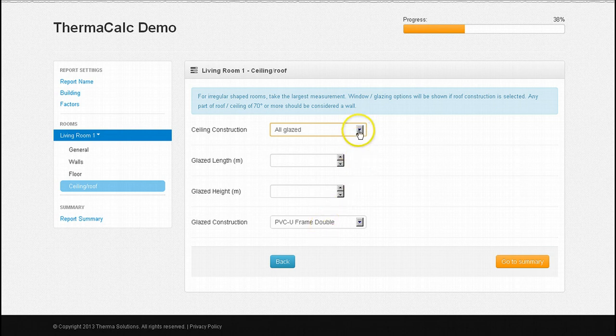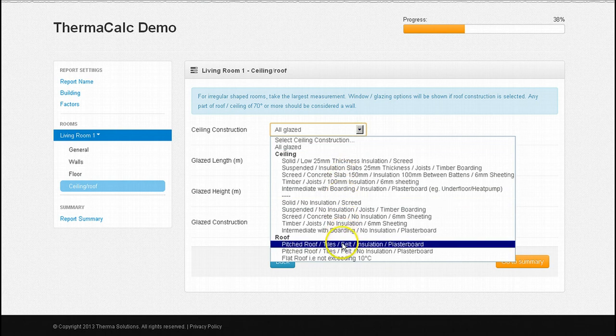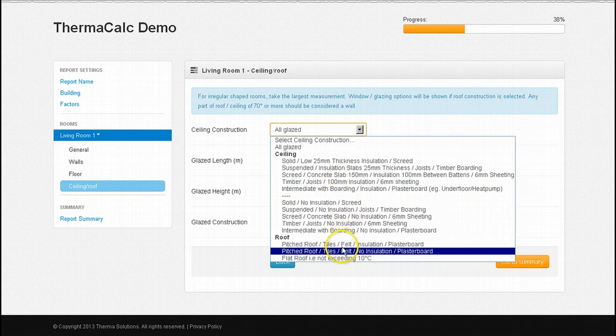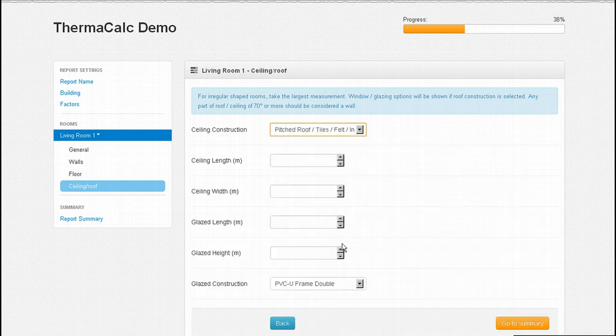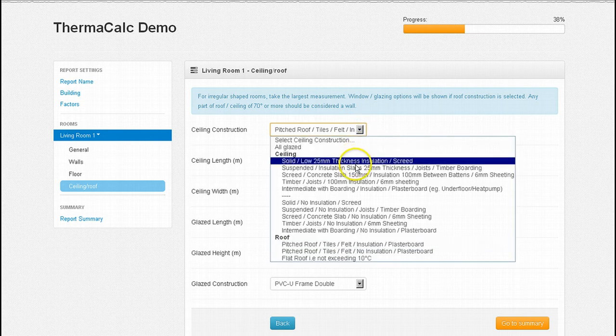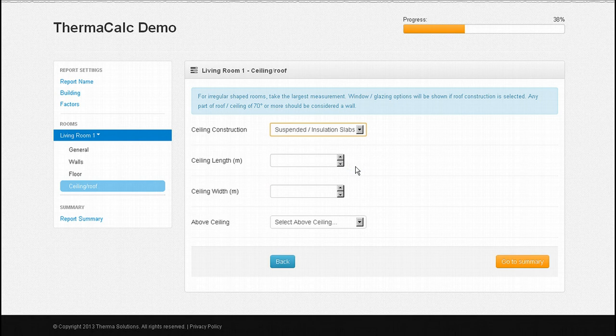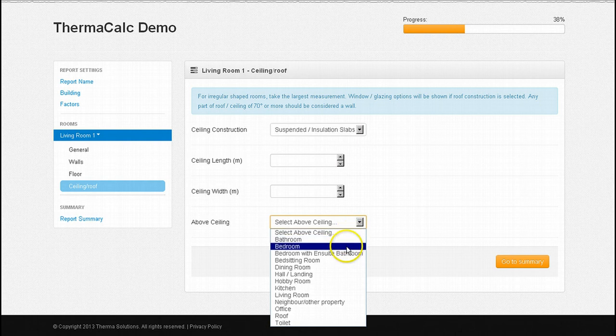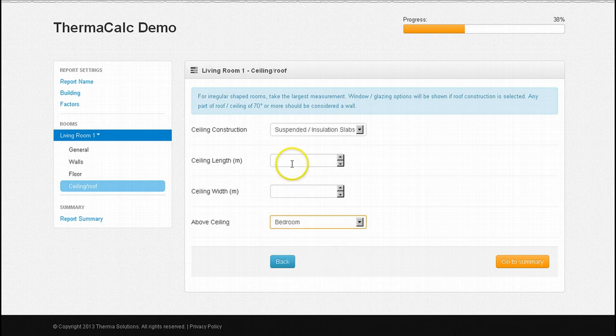If the ceiling is in fact a roof then we need to select a roof U value. The system now provides us with glazing fields to reflect roof lights or a similar construction. If the ceiling construction type is selected, ThermaCalc senses this to be part of the internal envelope so makes available the option of a room as being on the other side of the ceiling. In our case it's a bedroom and the measurements are 3 by 3. And that's it — all that's left is to go to the summary screen.